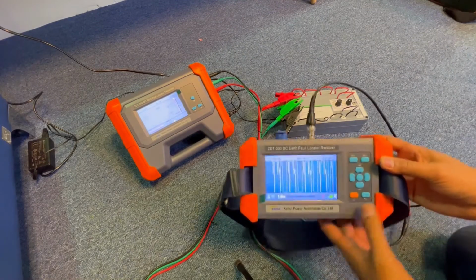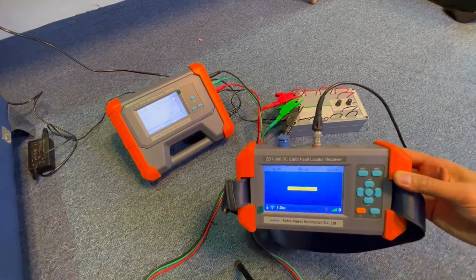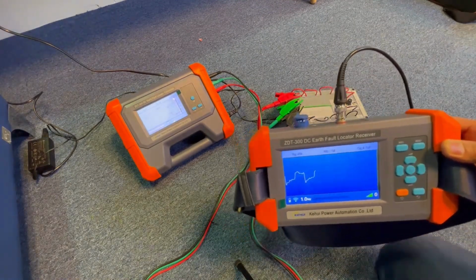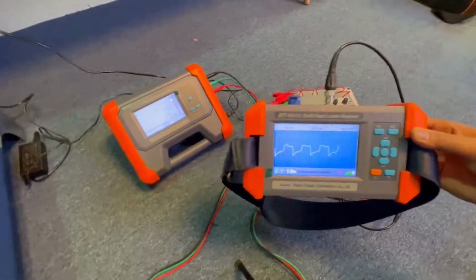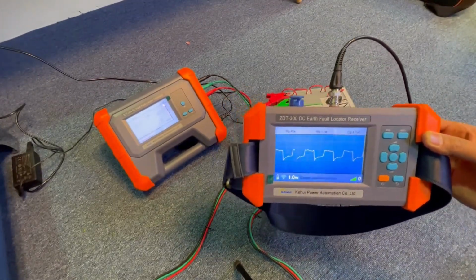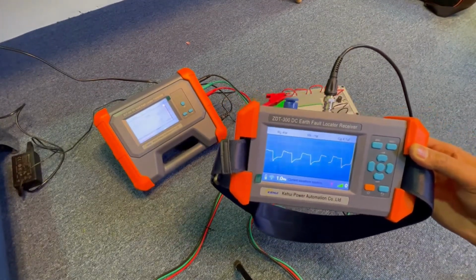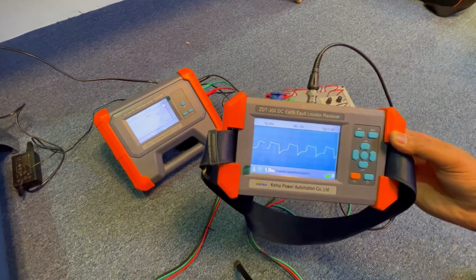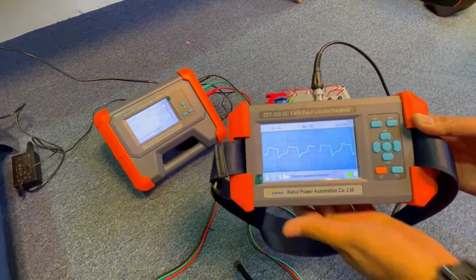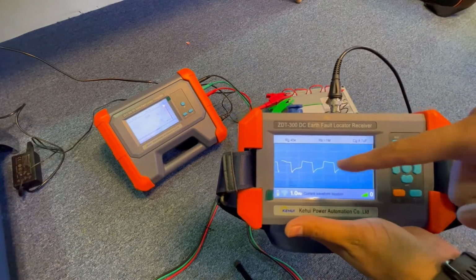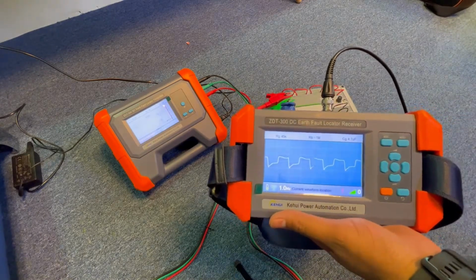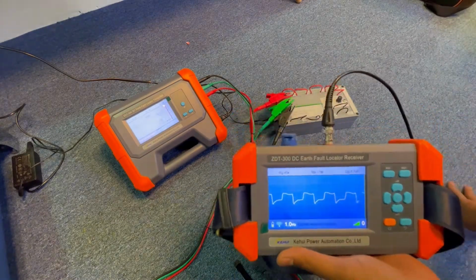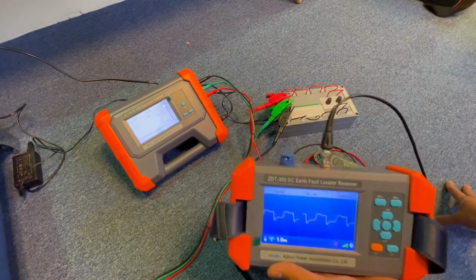So now in the receiver, just refresh and check whether it is faulty or not. It has already started sending the signal saying that there is already a ground in the system. If there is no ground, you will have a straight line. If there is a ground, then you will get a square waveform. So now let's see which is grounded, whether it is negative or positive.